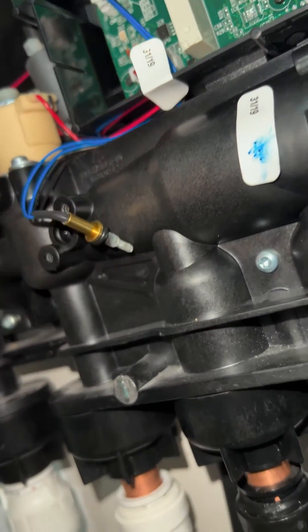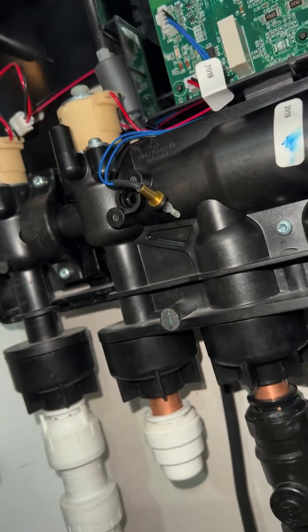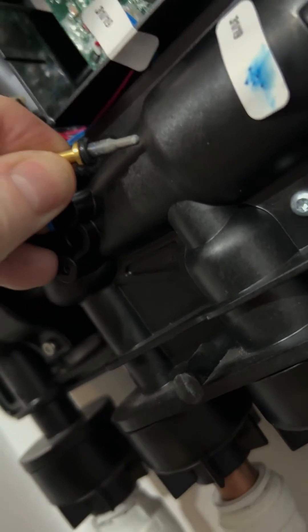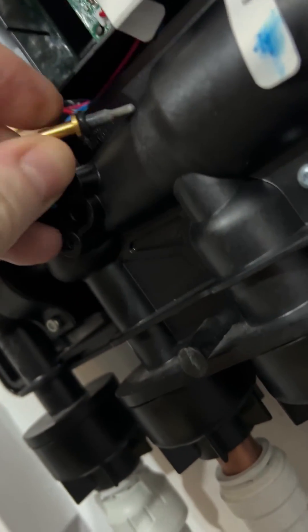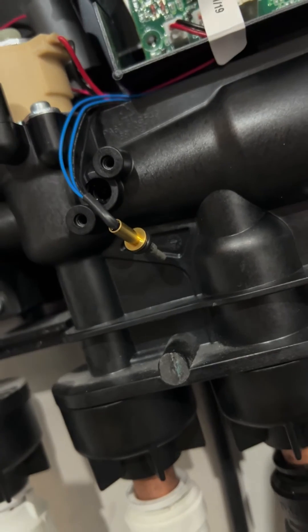I've given that a little clean off. The surface corrosion that was on it doesn't seem to have any problem. I think if it was burst, if it was rusted through, there would be water coming out that little hole and I would be seeing it. So when I said it's not corroded through, there's not that issue, but the thermistor could still be faulty.